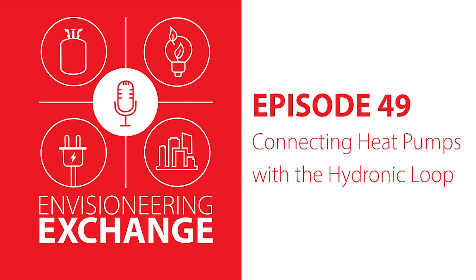Yeah, I think one of the things is buffer tanks, right? That's not always in the system, and it can definitely make the control of the heat pump a bit more stable. I think in general what you want is stability in the system and changes to be gradual and slow. This is done best if you have precise control, and if you make sure that you have no overflows, that you have the distribution properly under control.